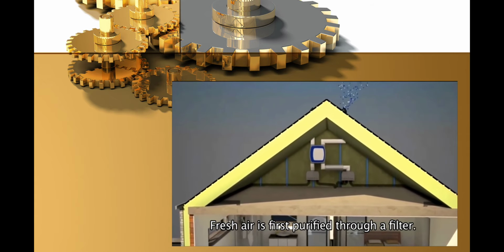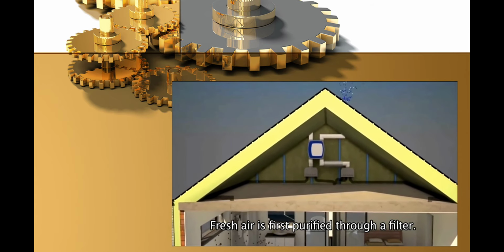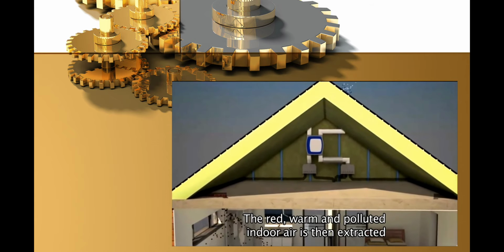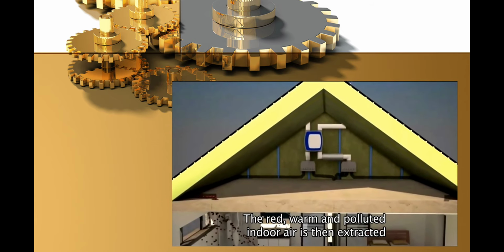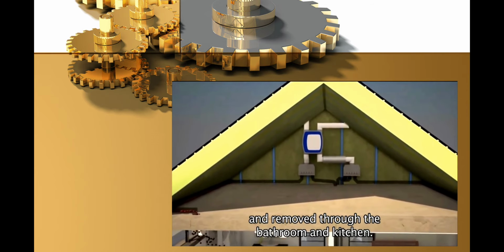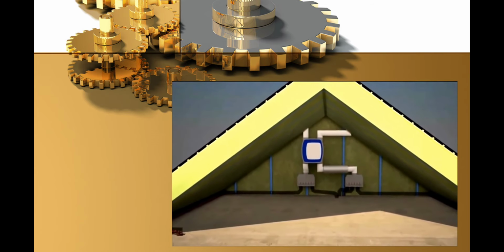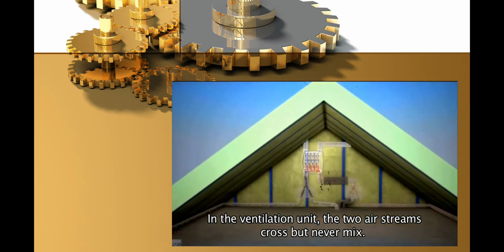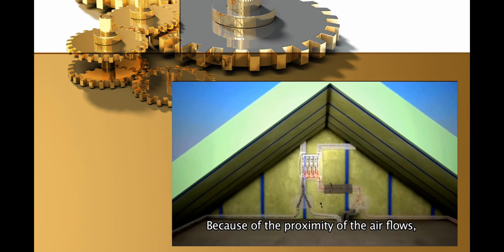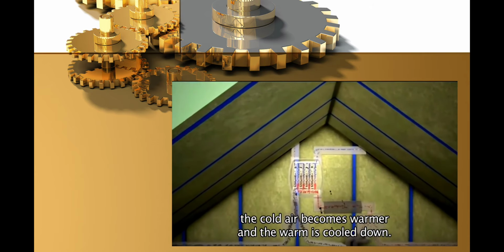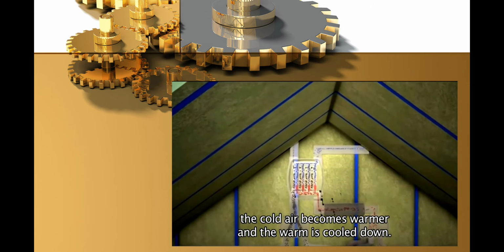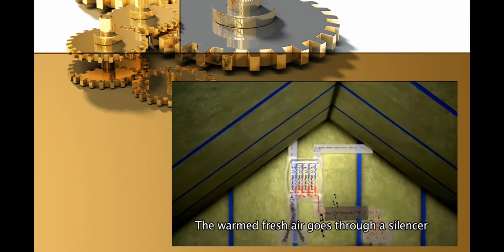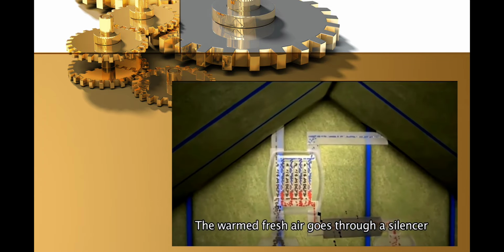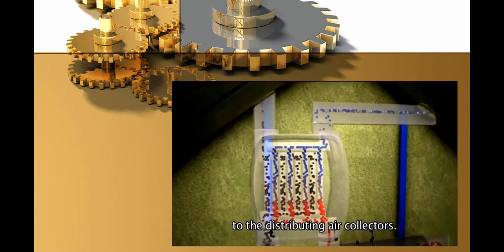Fresh air is first purified through a filter. The red, warm and polluted indoor air is then extracted and removed through the bathroom and kitchen. In the ventilation unit, the two air streams cross but never mix. Because of the proximity of the airflows, the cold air becomes warmer and the warm air is cooled down. The warmed fresh air goes through a silencer to the distributing air collectors.